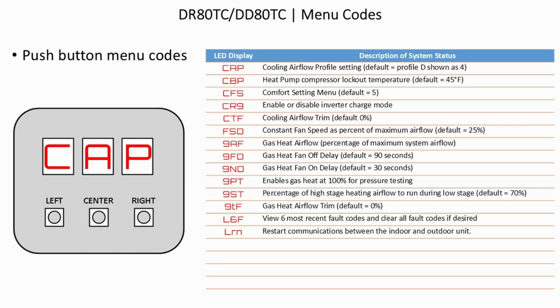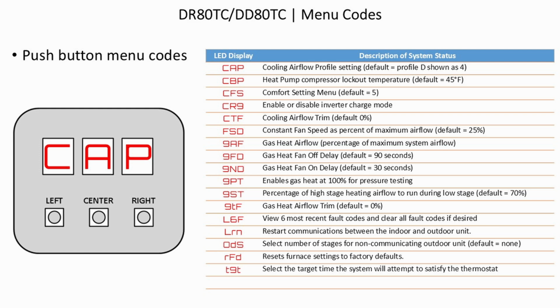LRN, restart communications between the indoor and outdoor unit. ODS, select number of stages for non-communicating outdoor unit, default, none. RFD, reset furnace settings to factory defaults. TGT, reset the target time the system will attempt to satisfy the thermostat. TON, indoor airflow for non-communicating outdoor units, default, 6 tons.